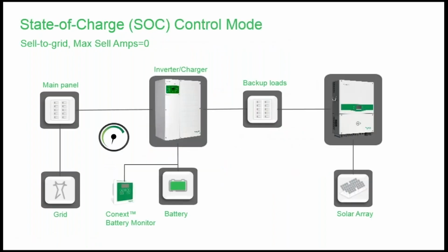So when you're using our battery monitor or a CAN bus compatible battery such as Discover, state of charge control is a feature that's exclusive to XW Pro. And this is really huge because of the fact that we just talked about: voltage control is really not very accurate when we apply it to lithium chemistry. So state of charge control allows the user to prioritize stored energy in an AC coupled or a DC coupled system. Battery monitor, Discover, or integrated battery monitor system can provide state of charge data to the XW Pro.